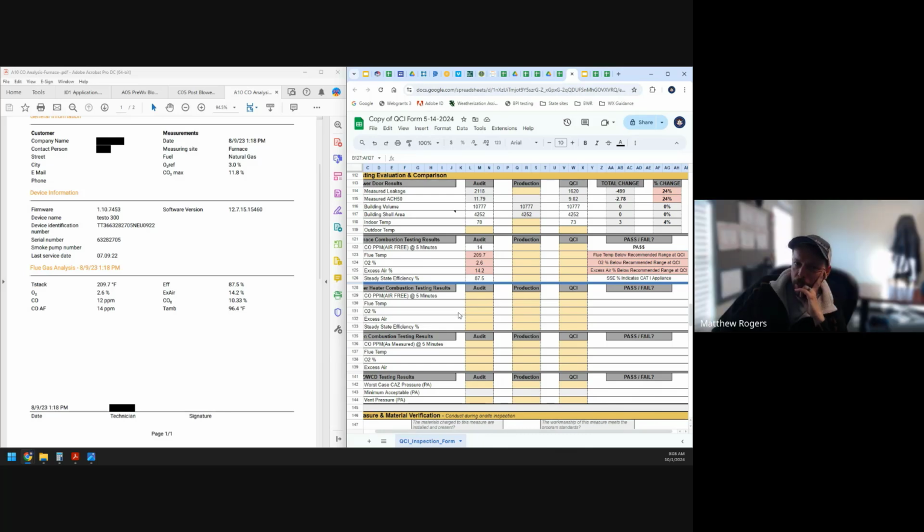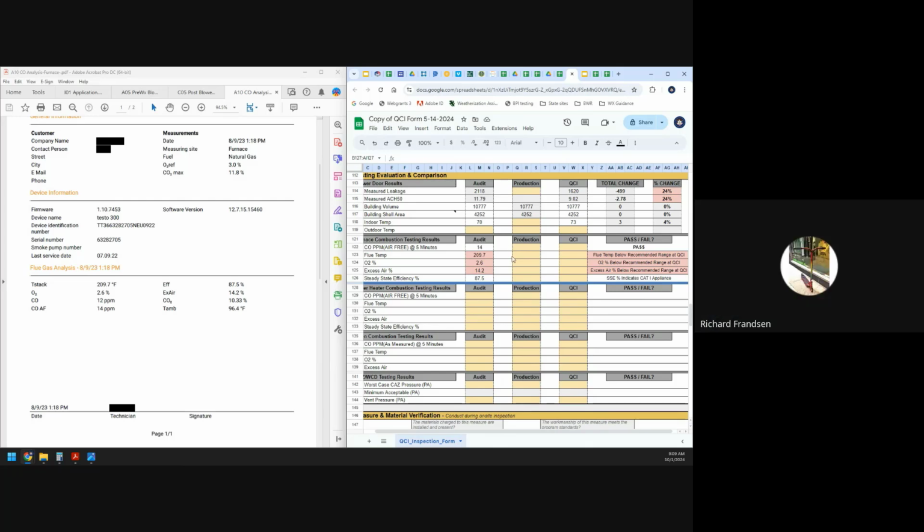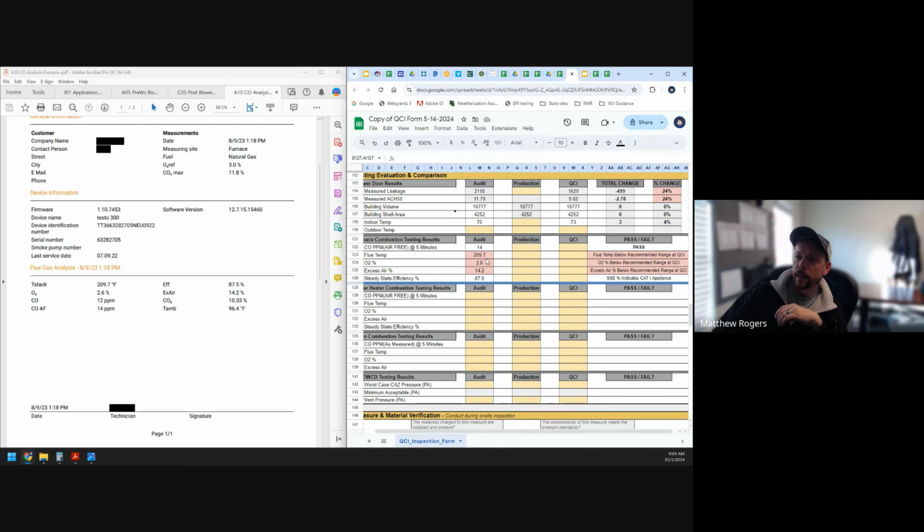Well, there's a couple of issues. Richard, Kyle, you guys can confirm this. The higher the oxygen percentage, usually there's a higher nitrogen percentage as well, and that typically cools your flame or your exhaust temperature. So my concern would be that right now this furnace seems to be running rich, so it's heavy in gas compared to how much oxygen it's got. If I change that mixture any more, it's going to lower my flue temp even more, and I'm going to have condensation going on.